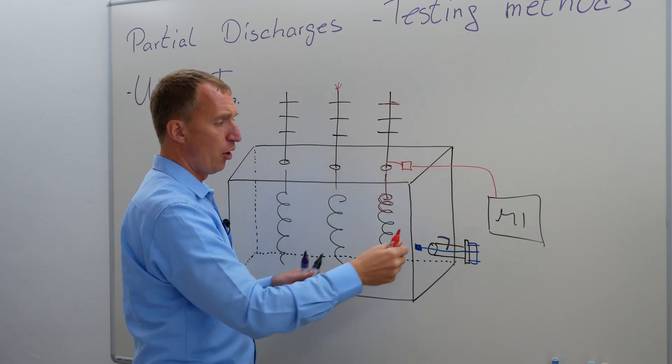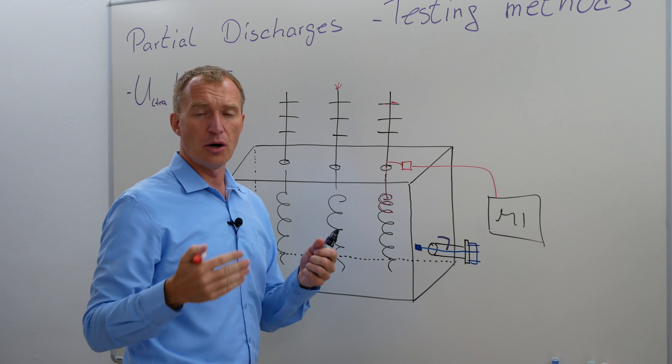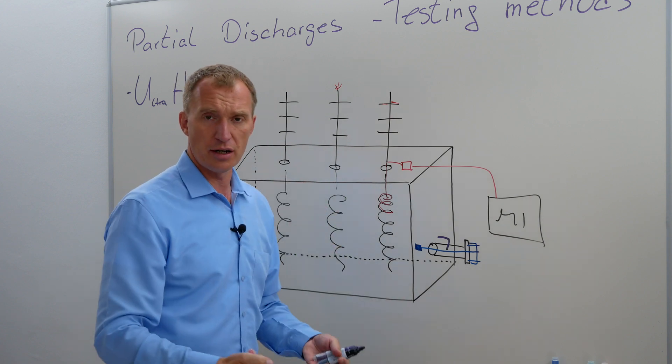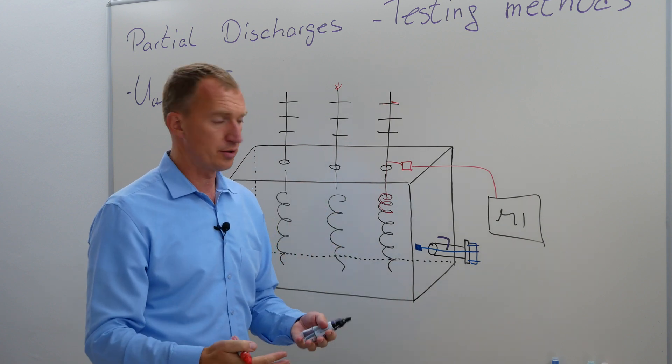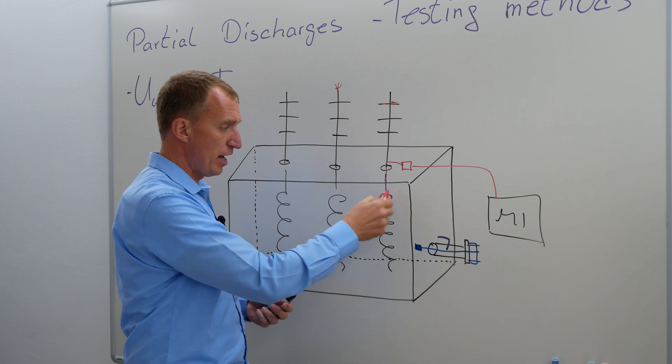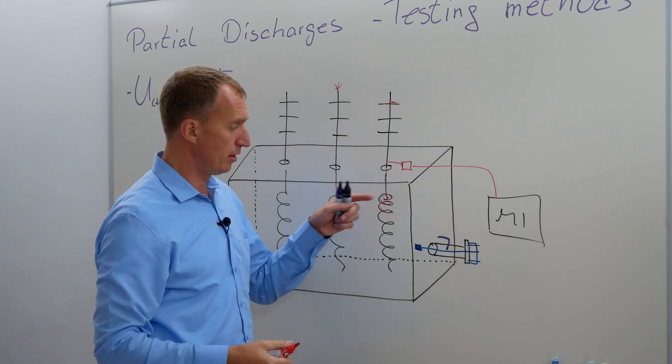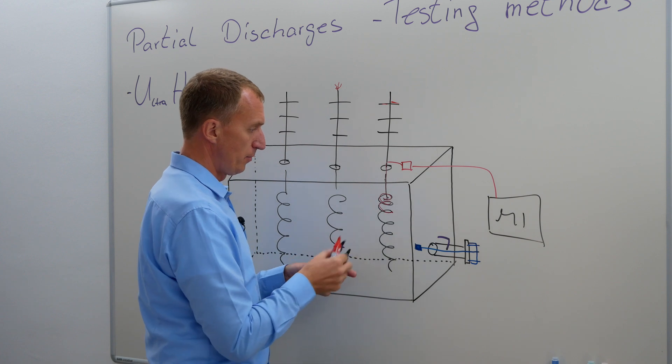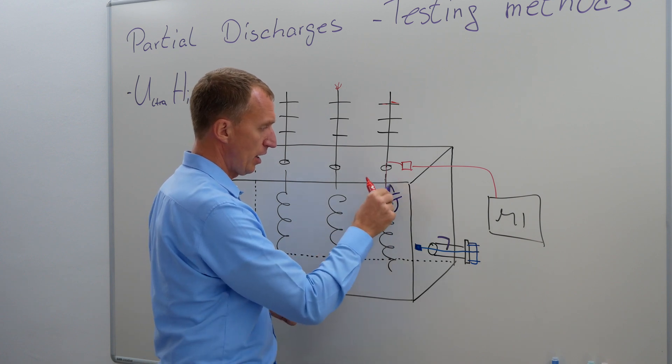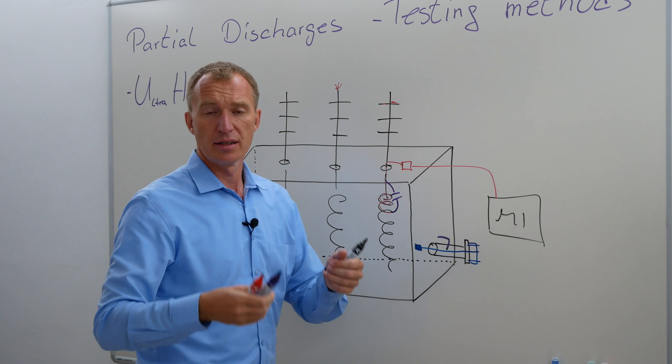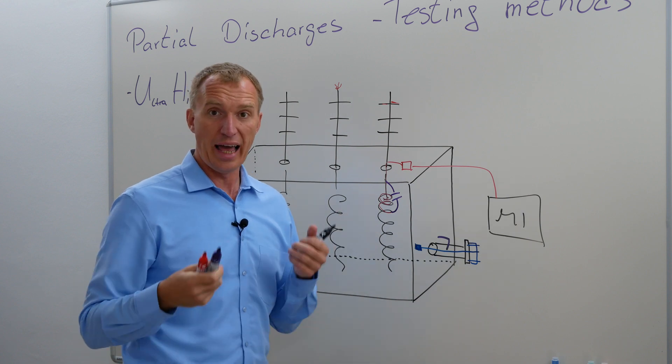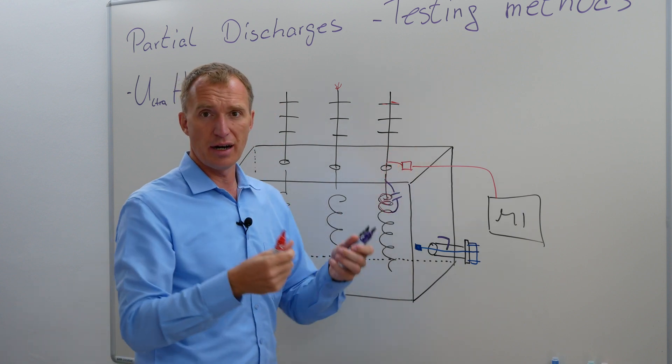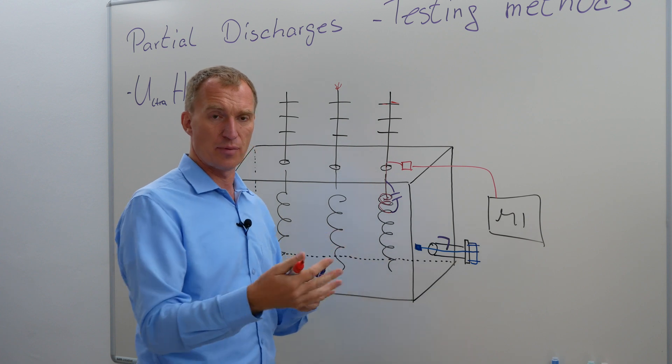By the time it already arrived at my sensor, I already lost some of the charge, and I lost a lot of the frequency content. It has to travel through the winding. Another possibility, there could be technically a capacitive coupling to here, but the signal is already altered. Once it is here, I have to figure out, is it from inside or from outside the transformer.